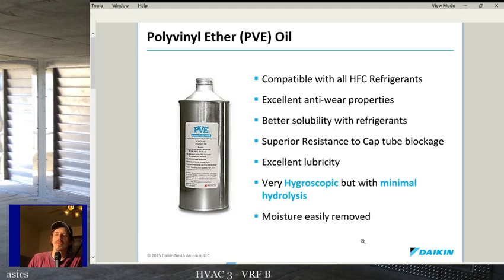With POE oil, it can be exceedingly difficult sometimes to get you down to a decent micron range once that oil's in there. So what I want you to remember off of POE versus PVE: with POE oil, it's extremely important that you minimize its contact with moisture as much as possible. With PVE, you still want to do the same, but you won't have as many issues when that moisture gets in there, as long as you perform a good vacuum.